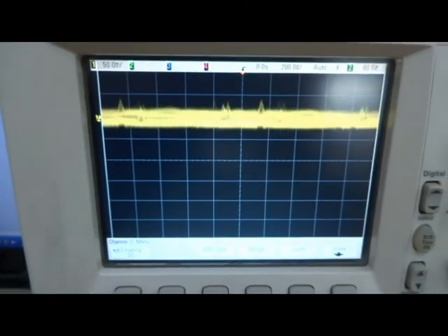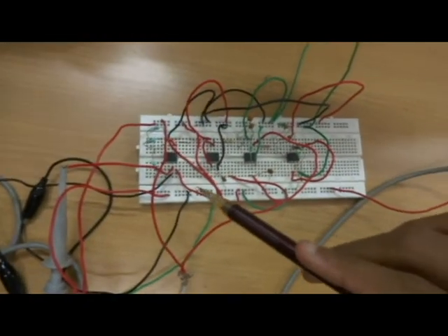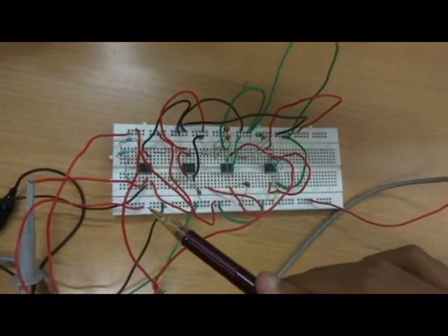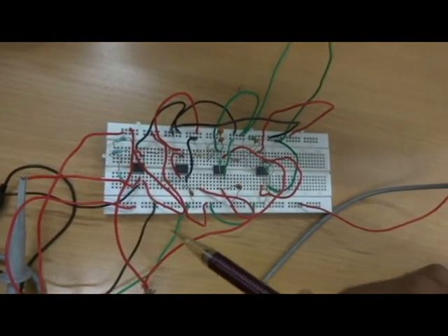It can provide a wide variety of gain between 1 to 10,000 and also it has a very low internal noise. The IC does not contribute to the noise in the ECG signal.